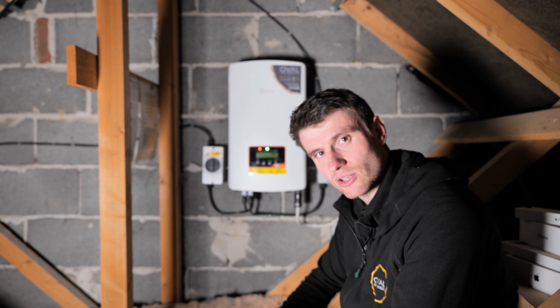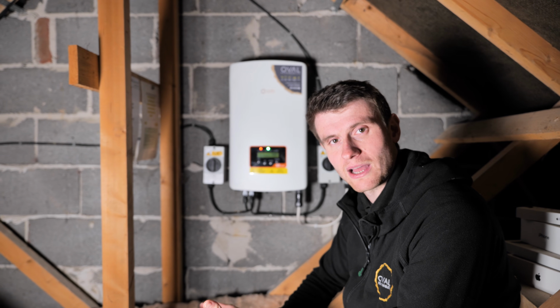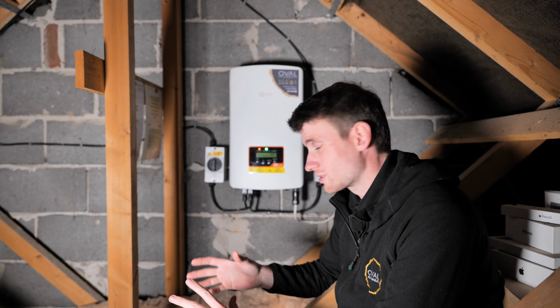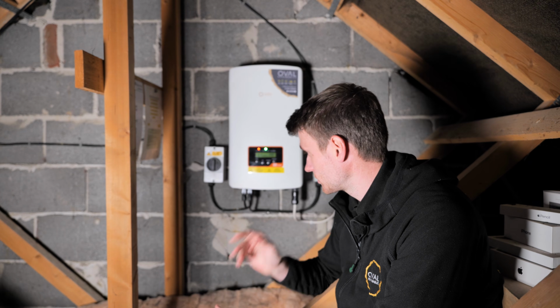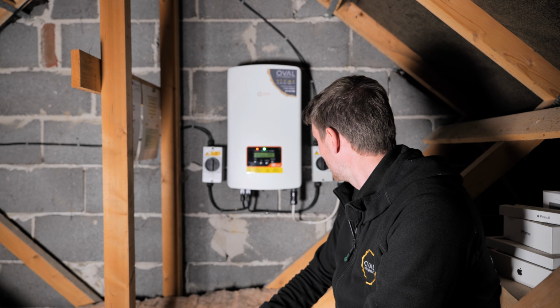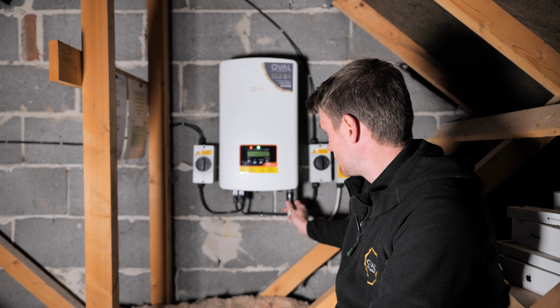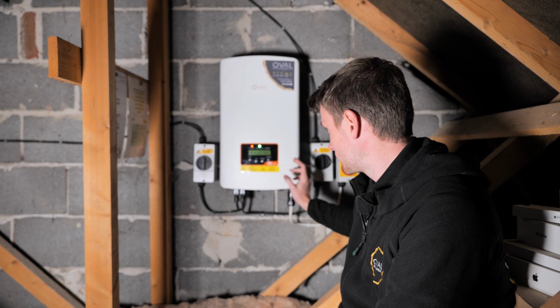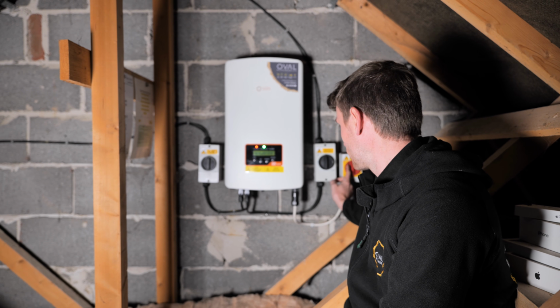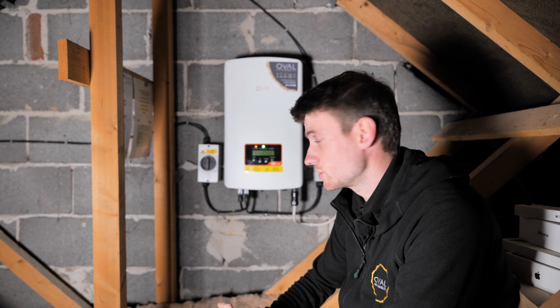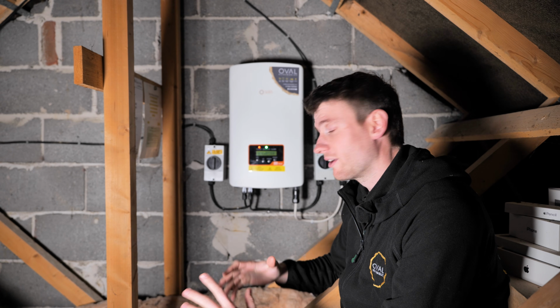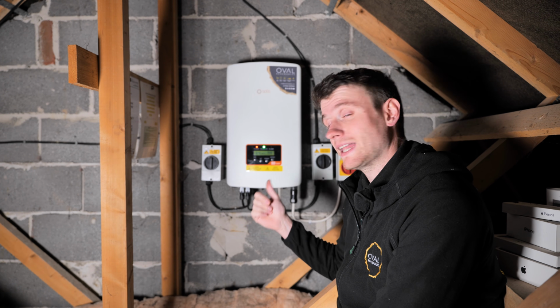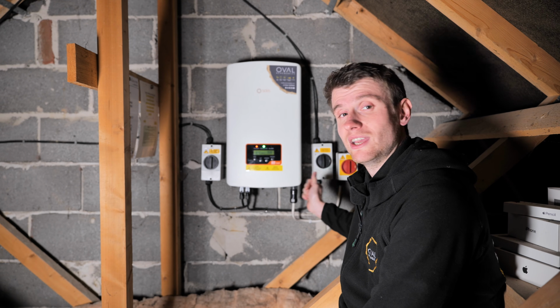I also re-terminated all these isolators because none of them had bootlace ferrules. I checked all the torque settings on the DC isolators too, just to make sure they weren't over tightened or under tightened, and made a new plug onto this cable so it fitted into the inverter, and checked all the connections in the AC isolator here. When these inverters are installed away from the main distribution board, a bit like the battery, they need another AC isolator.